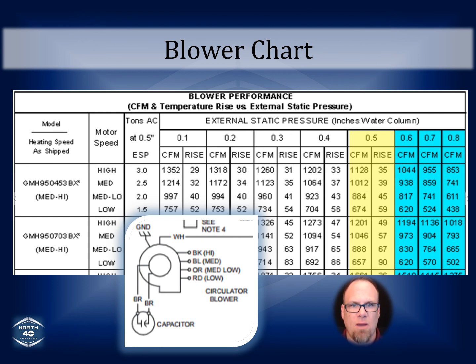Once you figure out what those are for each fan speed, you go to that static resistance, go down the column, match it up with its corresponding CFM value, and set up your blower according to 400 CFM per ton for this manufacturer, and for most manufacturers, or 350 for just a few of them. But know what the manufacturer actually wants and set up that blower speed according to that.